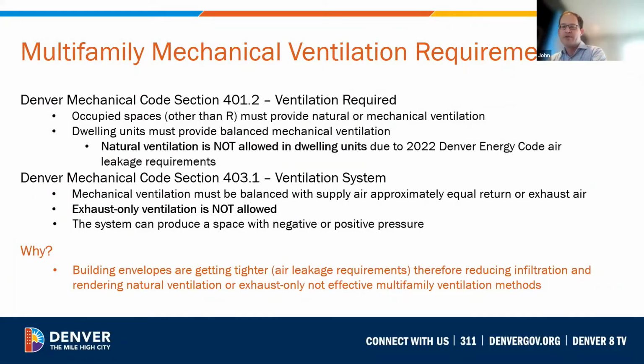As is common in other jurisdictions that use, say, a continuously running bathroom exhaust fan to provide ventilation for dwelling units, this option is not allowed in the Denver Mechanical Code and the Denver Building Code.